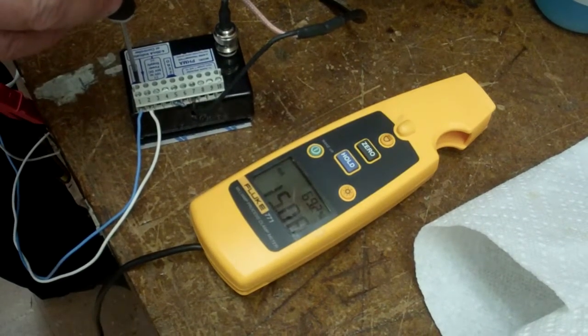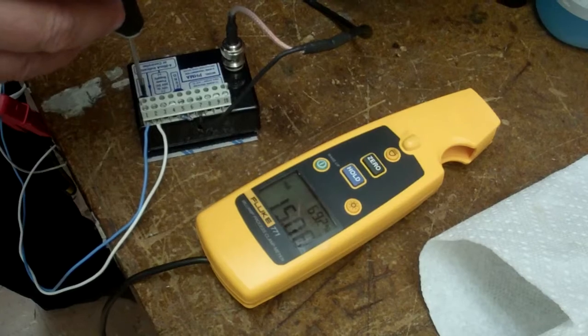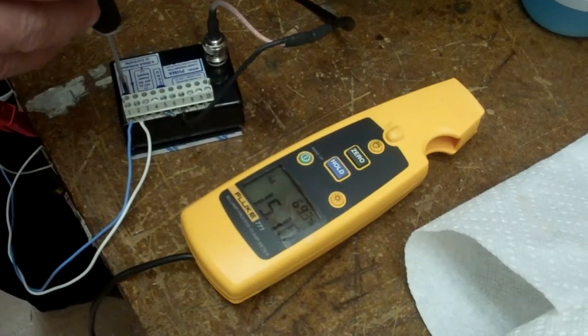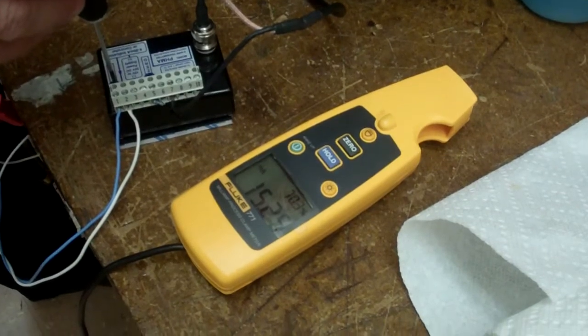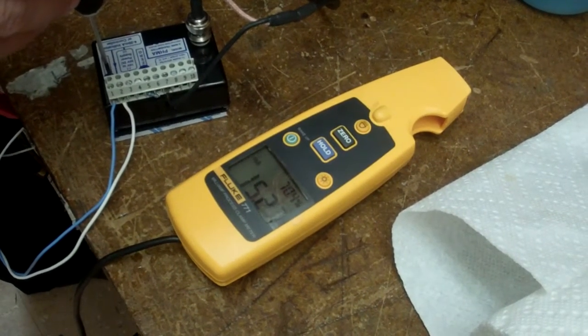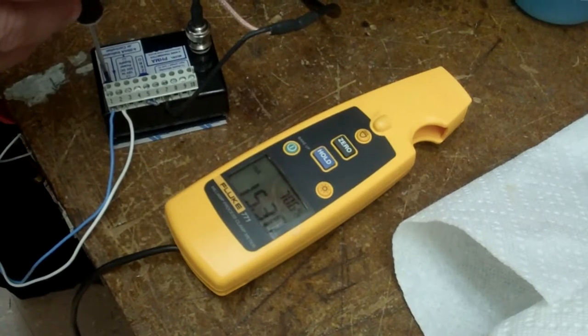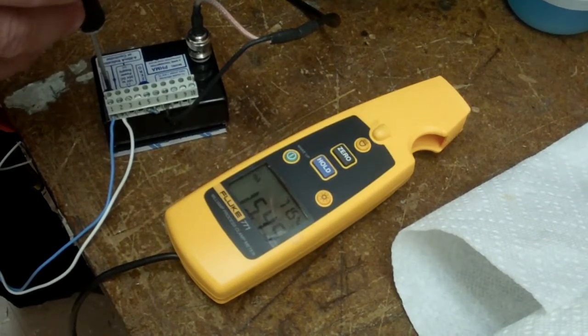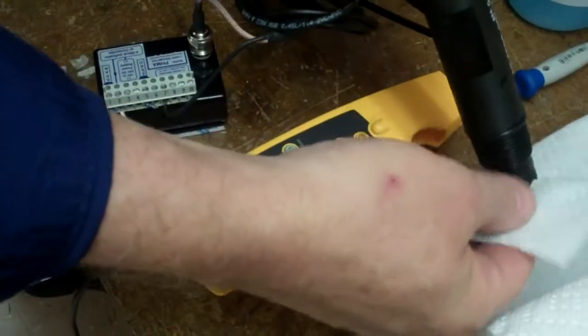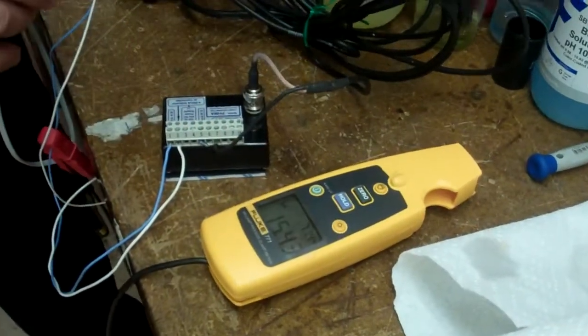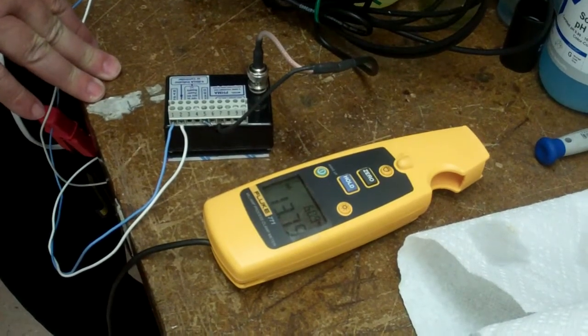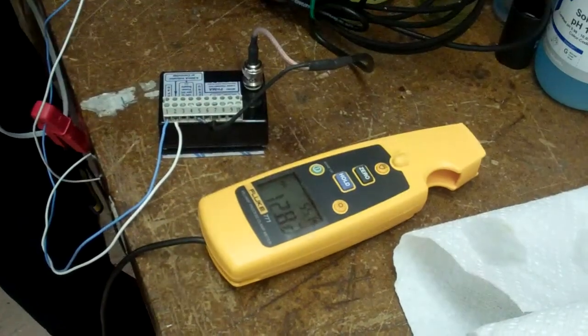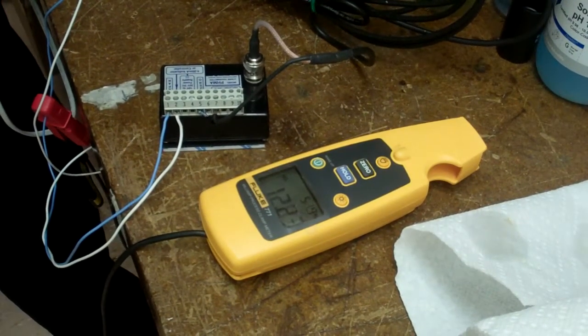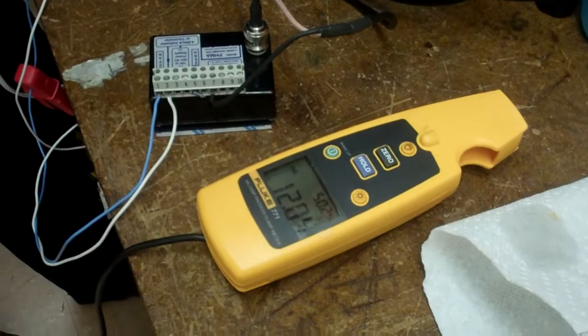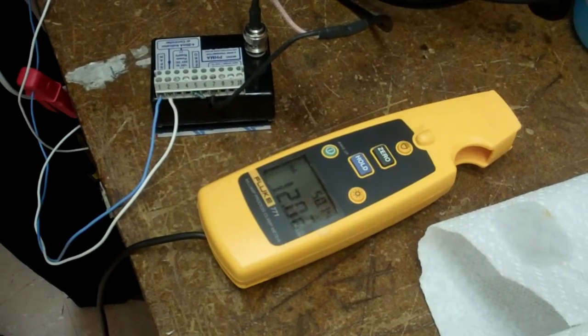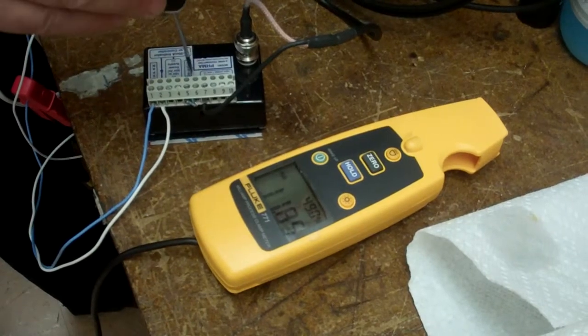Turn it. It's very sensitive. The span's a very sensitive adjustment. It's a little bit, it's a lot of reading change. There, 15.45. Dry it off. Back on 12.2, 12.04, it's going to go under just a little bit. I'll bring the zero up.